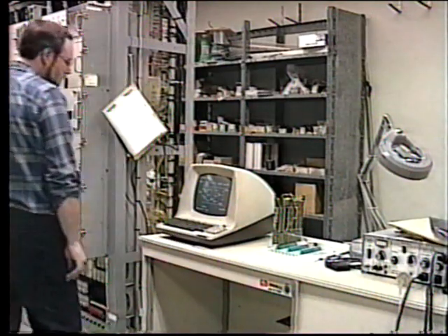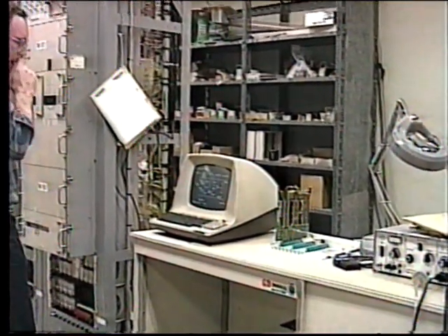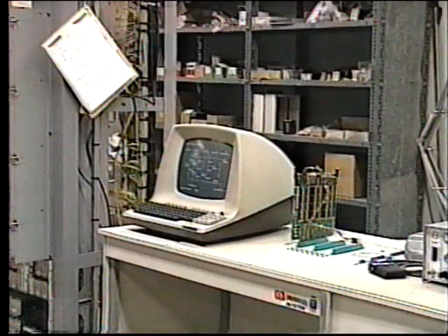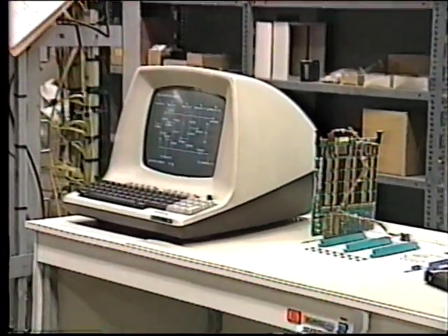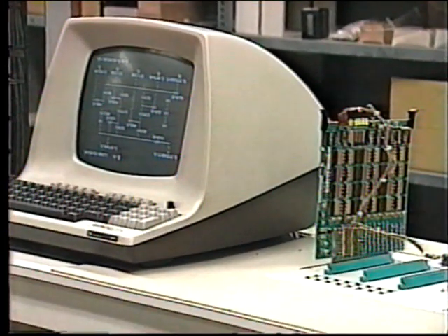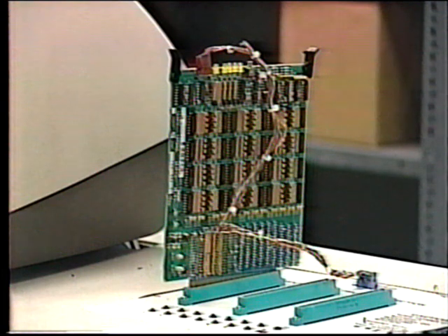Most of the maintenance activities are involved with tracking down faulty logic cards and replacing these with spares. The faulty cards can then be returned to the equipment supplier or perhaps to the company's own central workshop for repair and adjustment.